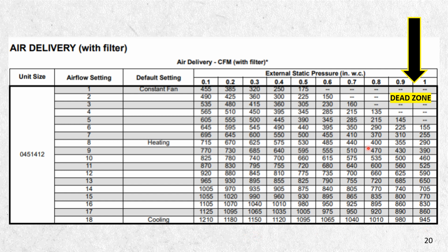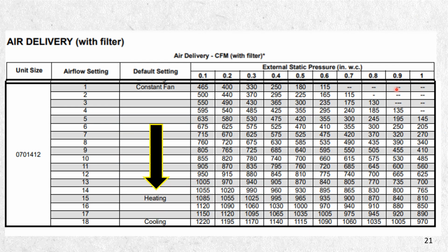So this is why this stuff's critical. And then look at in heating, if you're at cooling and it's 1.0, your heating is going to probably be somewhere in this area, maybe here, but you're looking at 400 CFM in heat. So you can see why it's so very important to check that static pressure, because they want this one set right here around 700 CFM in heat, and then here in your cooling around 1095 to 1100. This here, and also, these are the dead zones. So if your static pressure is 1 and you've got your fan on low and you're in this area, you have got some major resistance, and your blower motor will eventually burn itself up, and also you'll probably lose a compressor as well.